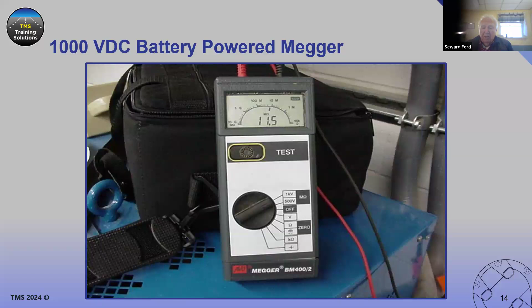In that attachment a few slides back, someone did testing: measuring 1,000 volts on a circuit and getting 33 megohms. Then he tested it with a 5,000 volt megger, and the reading dropped to about 13 megohms, because the additional voltage created new paths for current to leave the conductor through the insulation. When he went back to measure at 1,000 volts again, the reading stayed at 13 megohms — the damage had already been done by the high voltage test. That's something to bear in mind, as was just discussed a moment ago.